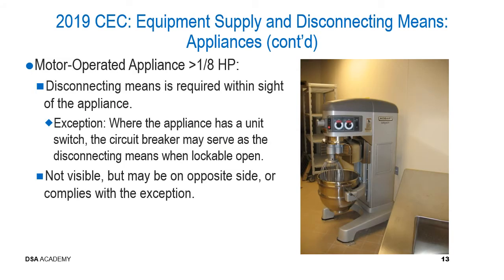The image shown here on the right is a gigantic mixer. You could basically call it an industrial mixer, and it's a motor operated appliance that is greater than 1/8 horsepower. And as we just discussed, the disconnecting means is required within sight of the appliance. But also, as we just discussed, there were several exceptions. And one of the exceptions obviously is where the appliance has a unit switch. The circuit breaker may serve as the disconnecting means when lockable open.